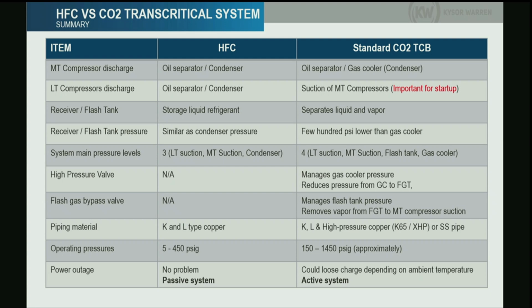But the point here is HFCs, we consider those as a passive system because nothing happens if you lose power. With CO2, we call it an active system because you need to do something to prevent losing the charge just by gaining heat from the ambient.